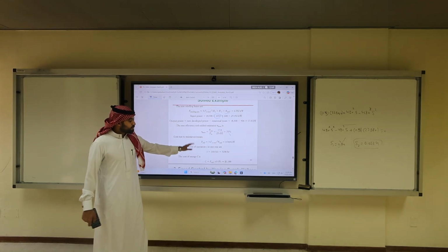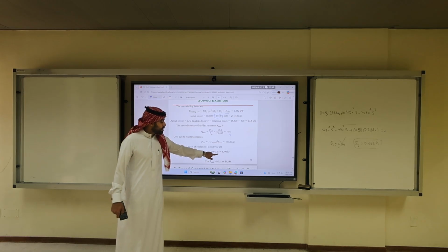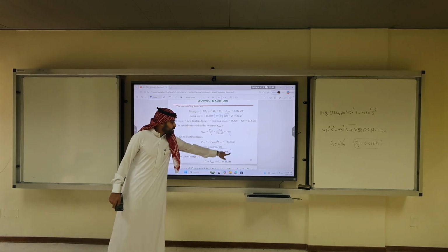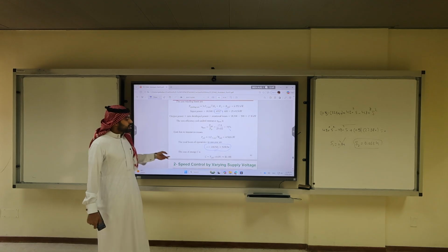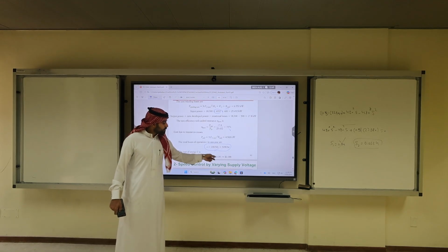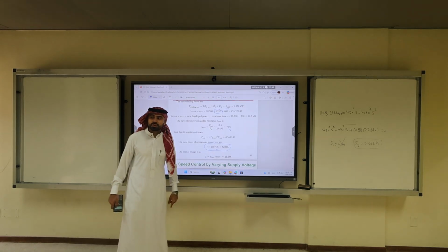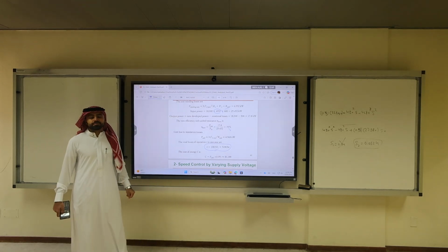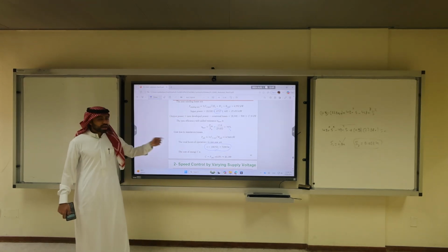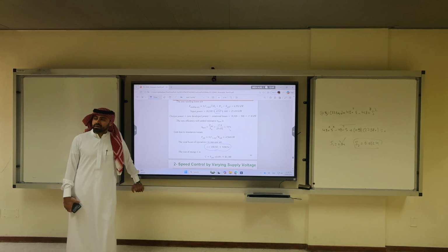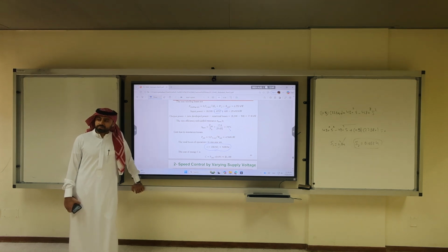And then you do the cost power calculation. In 1 year he runs it for 5,200 hours. You multiply it by 0.05 times the total power, and then you get $1,000 per year just for having an added resistance. You can resolve it now yourself. Okay? Clear?